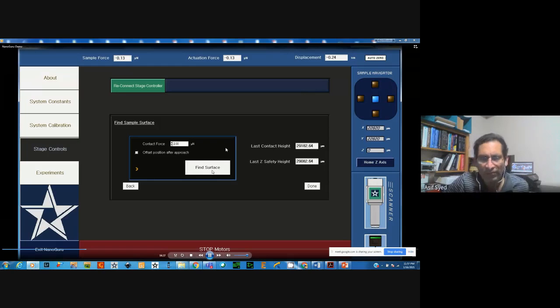Now if I click find surface, the sample will be underneath the tip, and the tip is going to approach the sample and try to make contact with the sample surface. Before doing that, it will ask you whether the tip is actually on top of the surface but not in contact, and then you say yes, and it will start to approach. Okay.